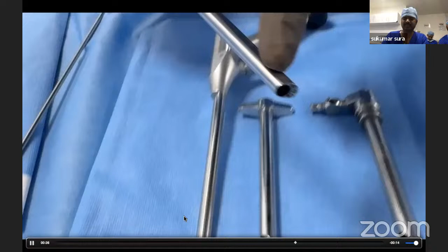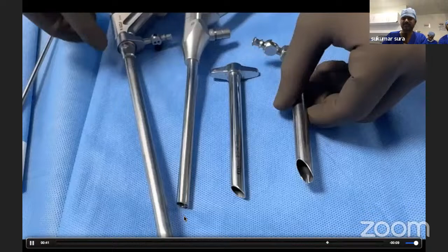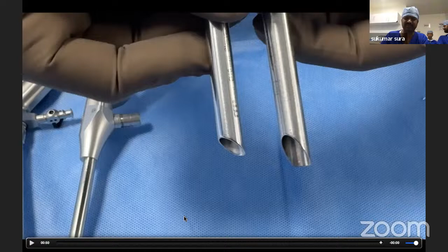a 20-degree scope. This is 5 degrees more than this. This is a 20-degree scope. And you see the bevel when compared to a 15-degree. So when you compare the scope as the degree decreases, the bevel has to decrease because it has to accommodate the angle. And if you are working with a more angled scope, your bevel increases, as a result of which the area of the field of view also increases.